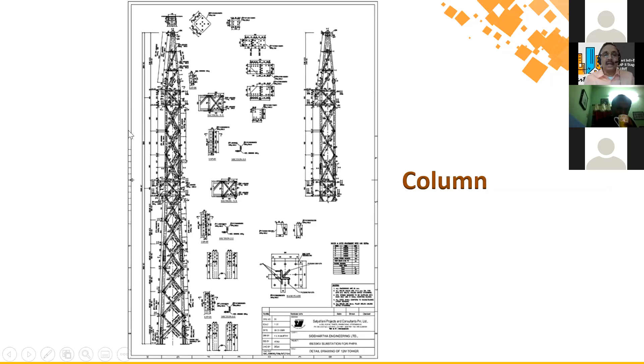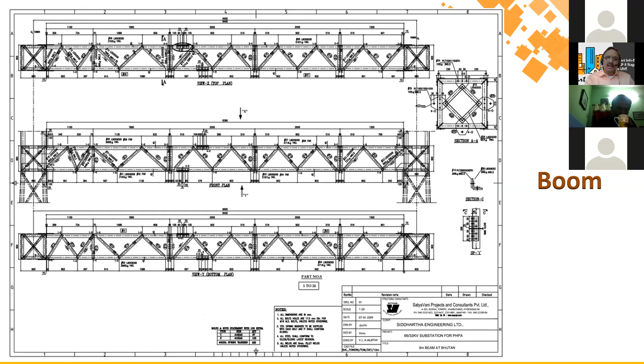And four angles vertical. And here you can see there is a girder here, and there is a girder at this level, and a peak for lightning arrestor or shield wire. So this is the boom drawing. Here you can see these are the connecting points for the conductor 1, 2, and 3. So these are the connecting points for the conductor. And you have the weight, vertical loads, tension from the conductor, and wind on conductor.